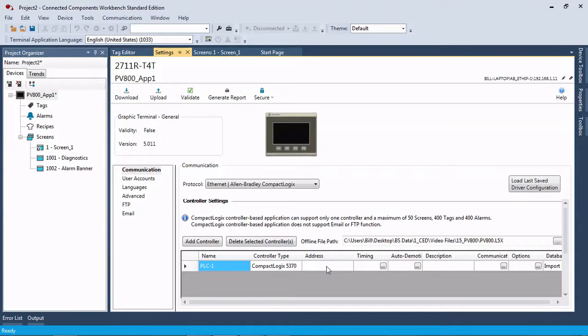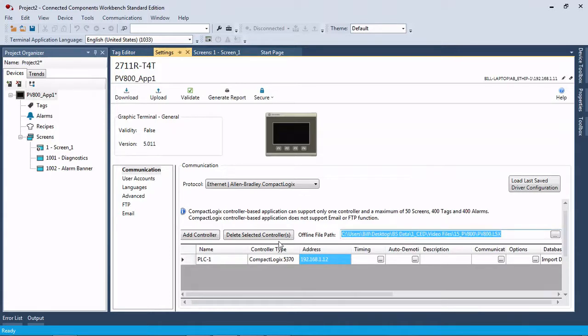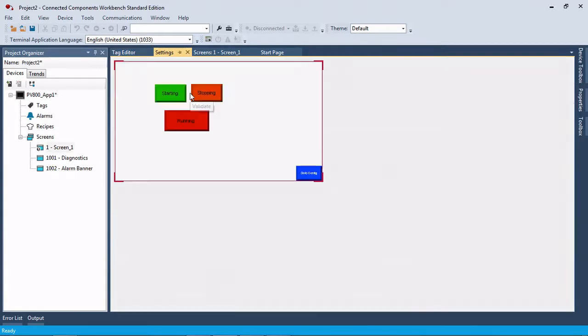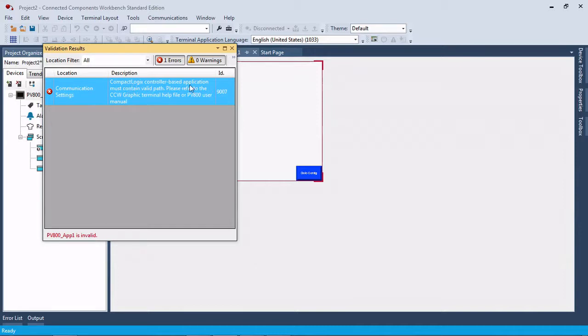Down here in the address bar, we're going to type in our IP address of the CompactLogix, and we're just going to leave it at that for right now until I show you something. We're going to go ahead and validate this. Now, we're going to get this error. This PanelView 800 app 1 is invalid. Why? Because our CompactLogix path is invalid.